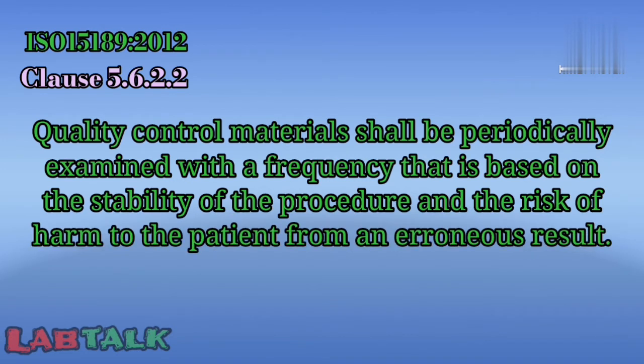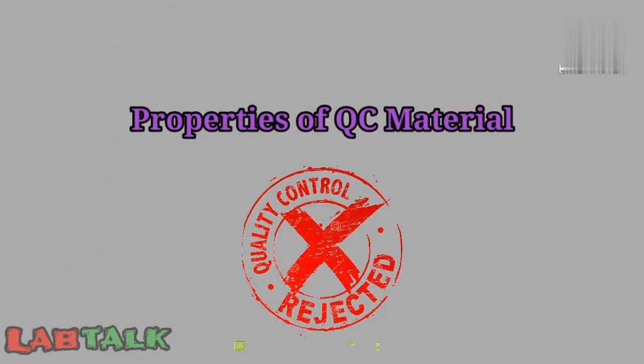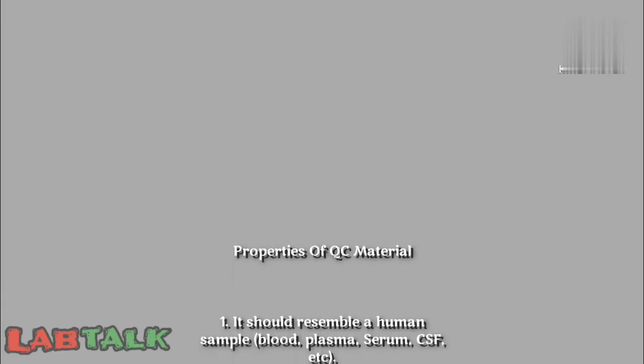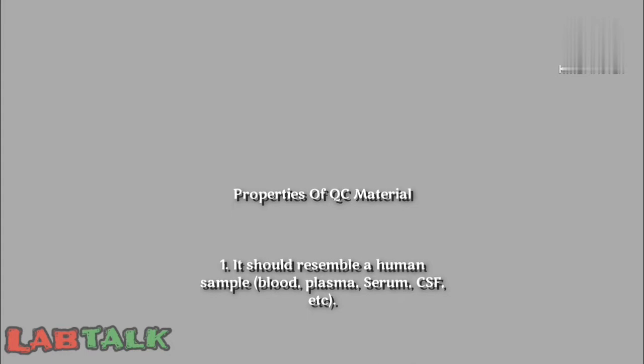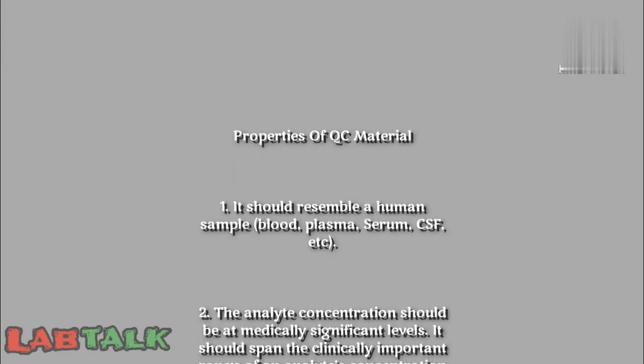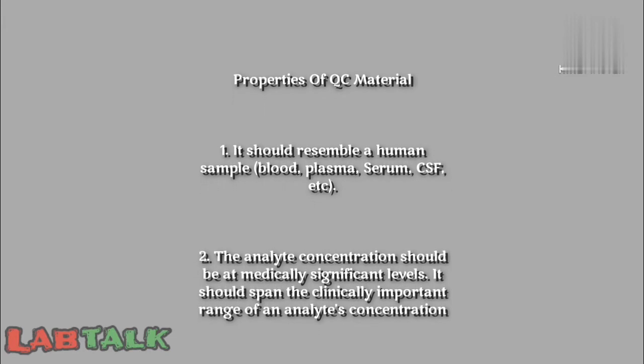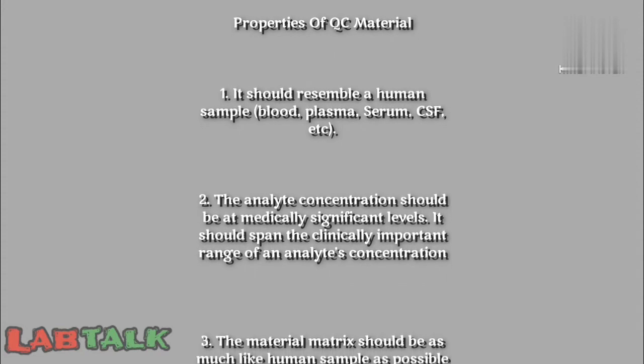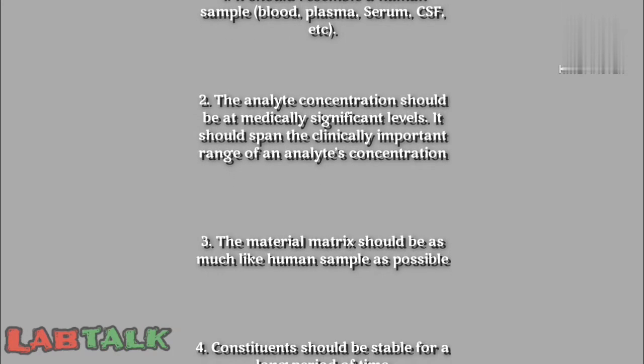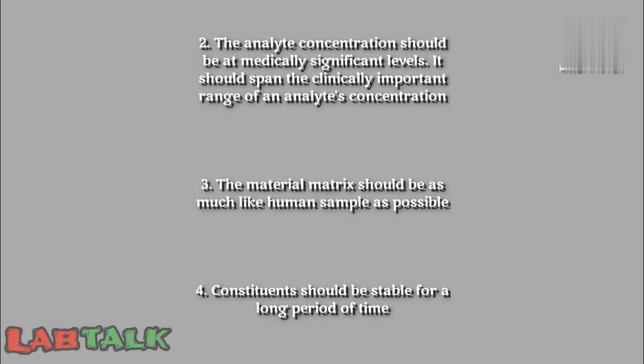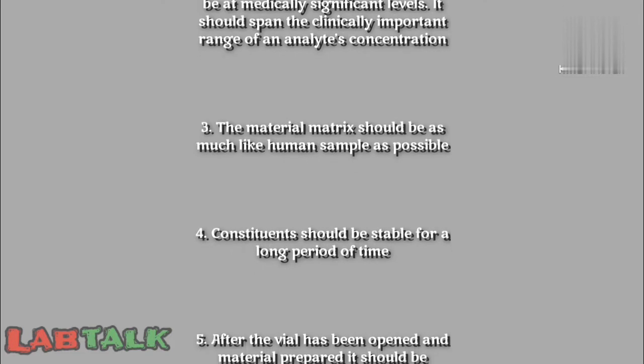When choosing a quality control material, there are important properties to consider. First, it should resemble a human sample — such as blood, plasma, serum, CSF, or other body fluids. Second, the analyte concentration should be at medically significant levels and span the clinically important range. Third, the material matrix should be as close to a human specimen as possible. Fourth, the constituents should be stable for a long period of time.